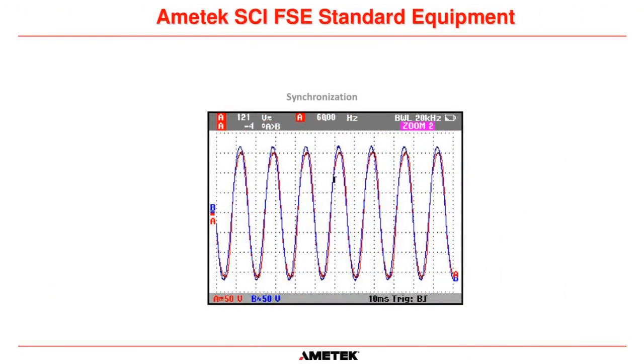Another waveform that we take is synchronization. We want to check that the bypass and the inverter are synchronized together. And we take this reading before we start our maintenance on the UPS, because obviously the UPS has to be synchronized for us to get it into bypass and perform the maintenance. And what we want to see is what you see here, that the red and blue waveforms are perfectly matched up. There's only 4 electrical degrees, as you can see here, between the 2 waveforms, and that's absolutely fine. We know that this UPS is okay to be transferred to bypass without any issues.